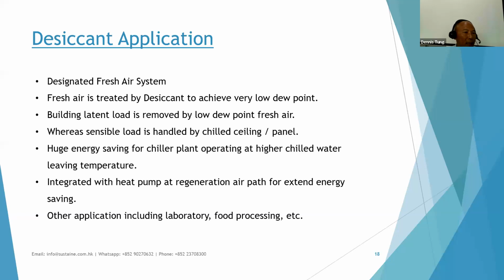Because we have, as I mentioned before, Hong Kong's high humidity, if we treat the fresh air with a desiccant method to achieve a very low dew point, we can use this low dew point fresh air to offset the latent load in the building. And then we can have another method to offset the sensible load of the building. In the building, the sensible load is quite high, quite a bit bigger than the latent load.